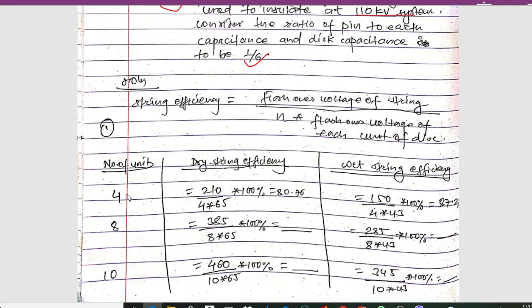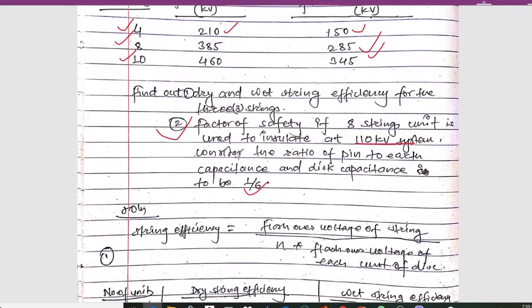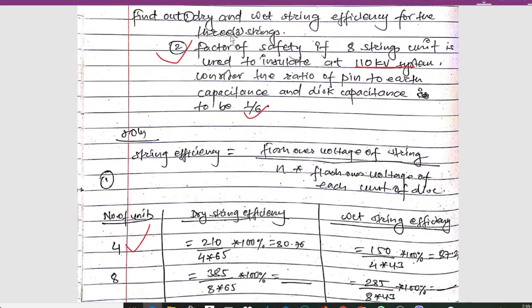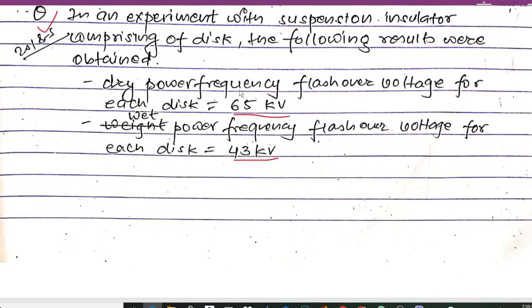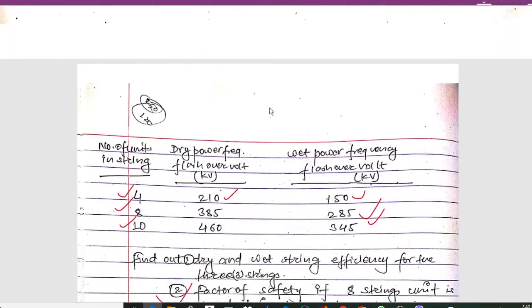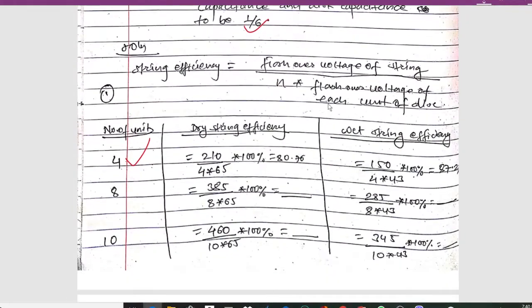For 4 number of disks, the dry string efficiency is calculated as 210 divided by (4 × 65), giving 80.76%. For the wet string efficiency, using 150 divided by (4 × 43), we get 87.2%.